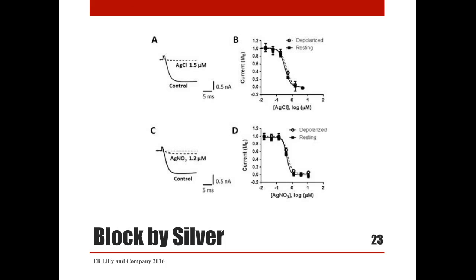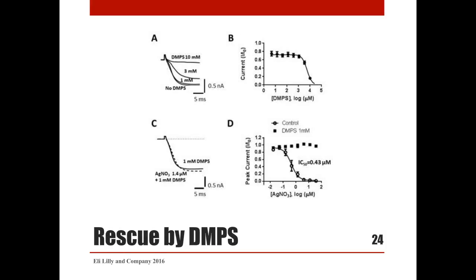Considering that silver-silver chloride is a major component of ground electrodes, and based on previous reports of T-type calcium channel block by silver ions, we hypothesized that the non-uniformity may be caused by silver ions coming off the ground electrode. We evaluated the effect of two silver salts on block of N-type calcium currents. Both silver chloride and silver nitrate blocked N-type calcium currents with IC50 of approximately 0.5 micromolar, and the block was not state-dependent.